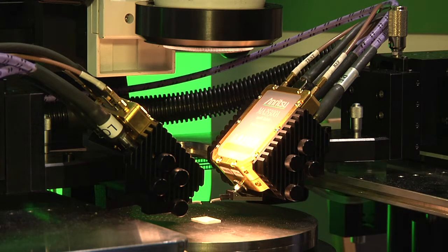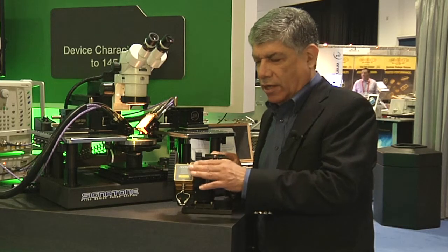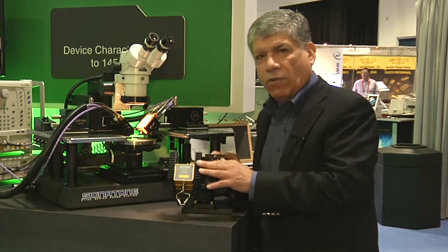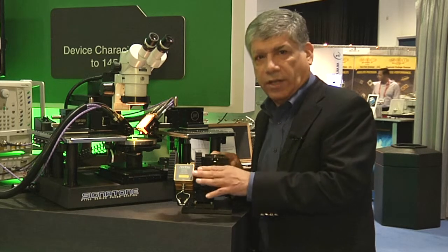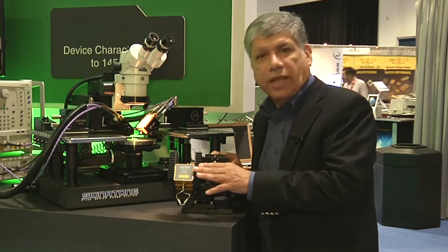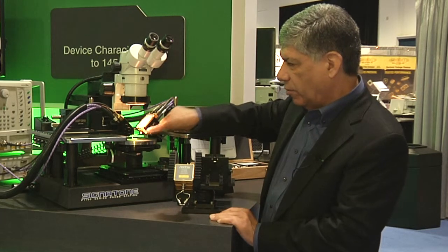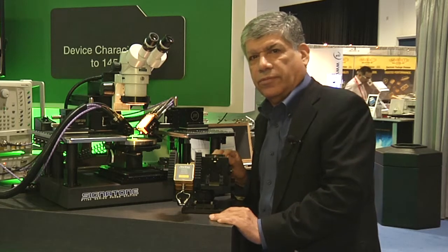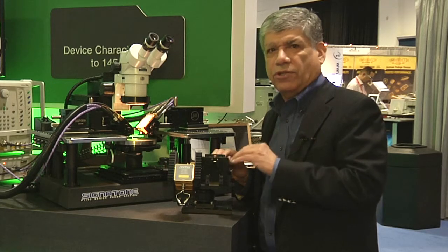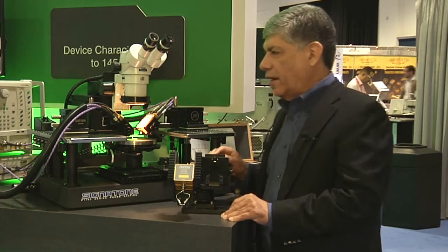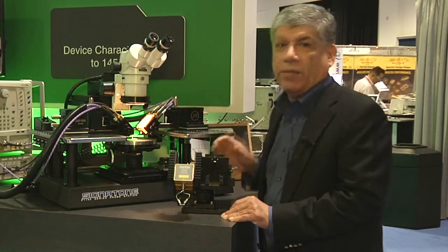So all of the benefits of the modules that we have been providing over the last couple of years up to 110 are part of the 145 system. So that includes things like true directivity for maximum stability and also widest dynamic range possible, because we can actually do a direct connect to the probes for on-wafer measurements. So on-wafer measurements is a majority of types of applications used for broadband systems, and therefore being able to mount the modules on a probe station is quite important.